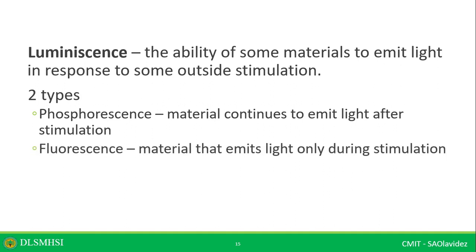Fluorescence, on the other hand, is the ability of a material to emit light only during stimulation. When the stimulant ceases, the emission of light ceases. Phosphor crystals of intensifying screens exhibit fluorescence. In fact, continuous emission of light from an intensifying screen after stimulation is undesirable, as this will cause poor detail images.